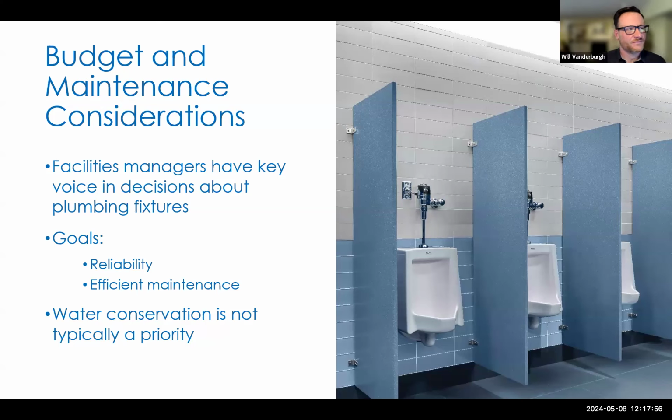Let's see. There's probably a couple of different things at play there. The first, they take a fair amount of force to activate, so frequently they're slammed or pressed firmly. In some cases, depending on the model that's out there, that top lever activator begins to break down over time and eventually fail. They rely on that spring maintaining tension throughout.